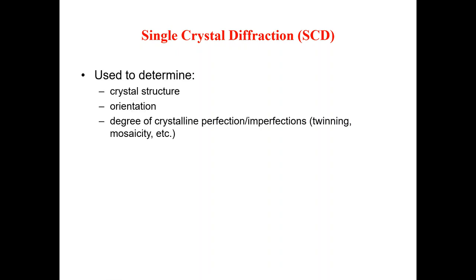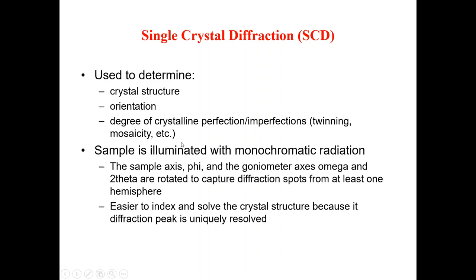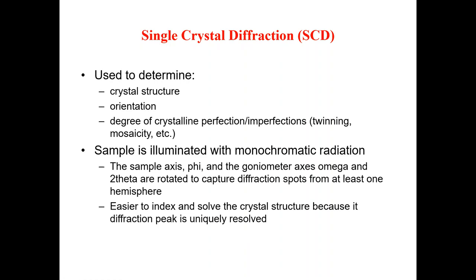Single crystal diffraction, called SCD, is used to determine crystal structures, orientations, and degree of crystalline perfection or imperfection — such as twinning and mosaicity. In this technique, the sample is illuminated with monochromatic radiation, and the sample axis phi along with the goniometer axes omega and 2-theta are rotated to capture diffraction spots from at least one hemisphere. This makes it easier to solve the crystal structure because each diffraction peak is uniquely resolved.